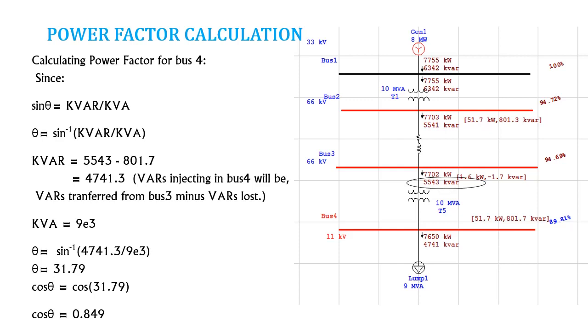will be actually 5543 minus these lost kVARs. So we are subtracting lost kVARs from the kVARs injecting from bus 3 and we have 9000 kVA since it is a 9 MVA load. And in this way we are calculating theta, taking the sine inverse of this term and then finding out the power factor. So the power factor at this condition is 0.849 or you can say 0.85 and our aim is to improve this power factor.